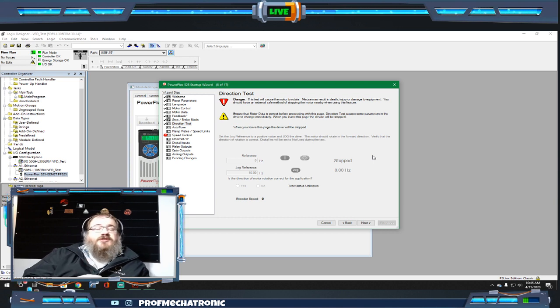So what you're able to do in this particular case, normally if you had a motor setup, which I do not, I only have the VFD set up, you would actually be able to jog your motor to different speeds. Now it's extremely important that you understand how your motor is currently set up and configured, because you do not want this to be attached to any kind of mechanical system. You want this to be a free running motor so that you can do the best check, knowing or checking to see which rotation you're actually running this in.